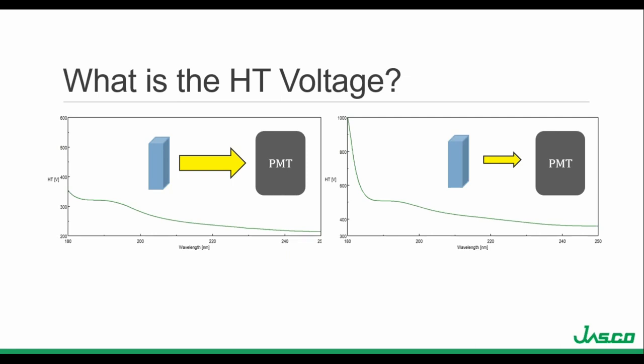Before discussing these factors, I need to explain the second most important piece of data to acquire along with the CD signal: the HT voltage, or high-tension voltage. The HT voltage is applied to the detector and used to amplify the signal and therefore the sensitivity. Since different wavelengths have different light energies, the HT voltage accommodates for fluctuations in the light level. It adjusts the amplitude of the signal depending on the DC voltage, which monitors the total signal output or total absorbance. When a sample has an optimal concentration, a sufficient amount of light is transmitted through the sample and reaches the detector, and the HT voltage is low.